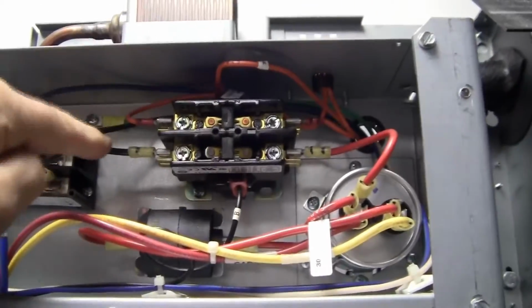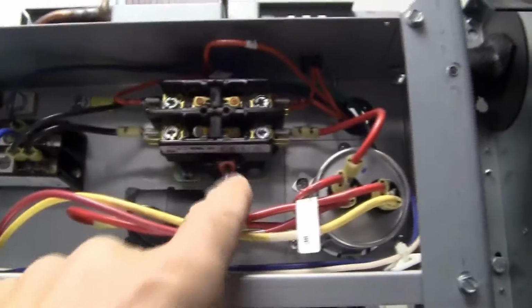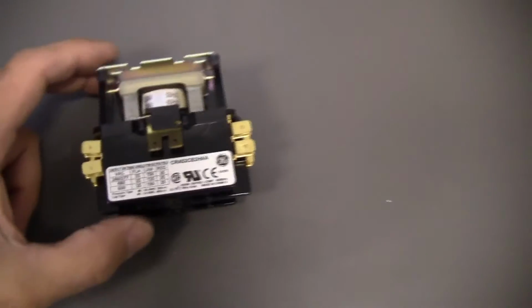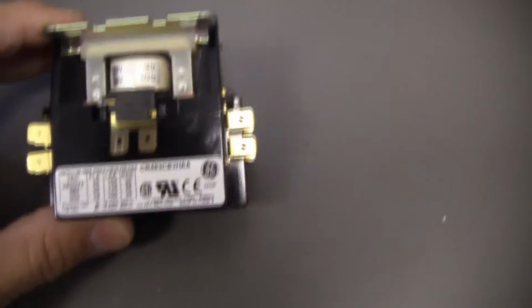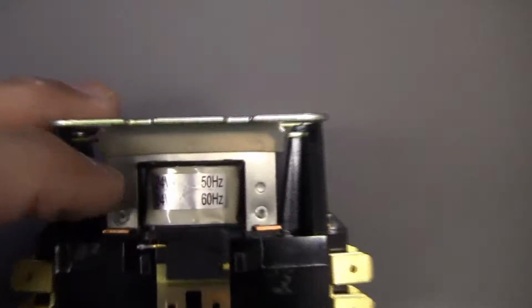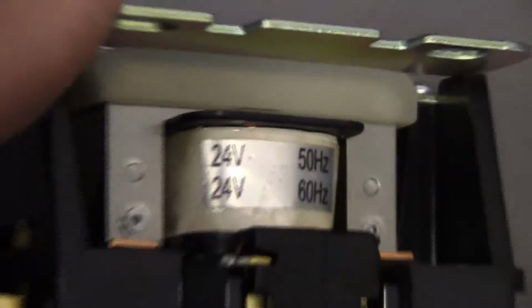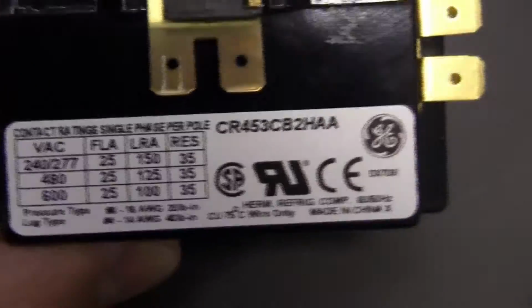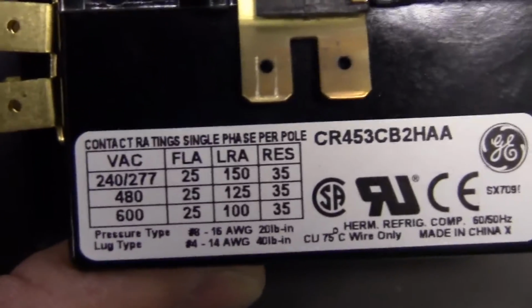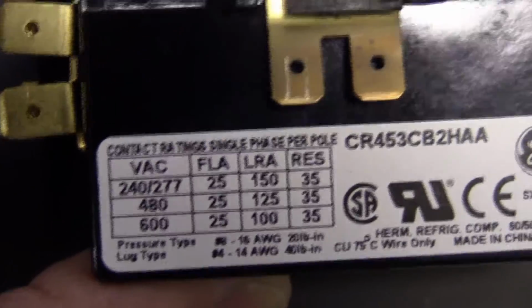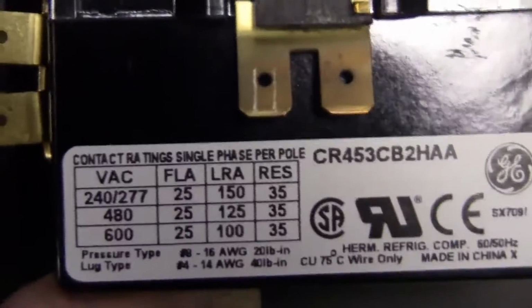And all I have to do now is pull off all my leads, unscrew my contactor, a couple of Phillips head screws, take it down to the supply house, get a replacement. All right, here's your contactor just sitting here on the table. And you can see here your coil voltage is 24 volts, tells you right there. And it tells you the rating of this full load amps. Now we're running 240 volts, so it's a 25 amp contactor. And of course it's a 2-pole contactor. There's a model number there, but I'm just going to take this right down to the supply house.